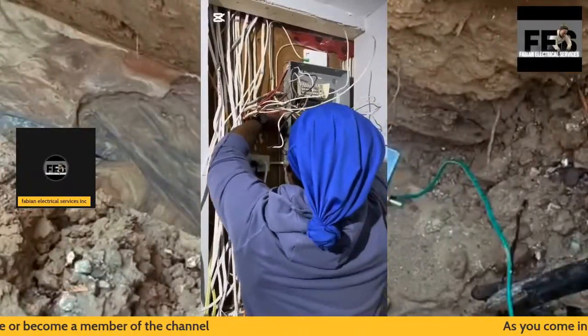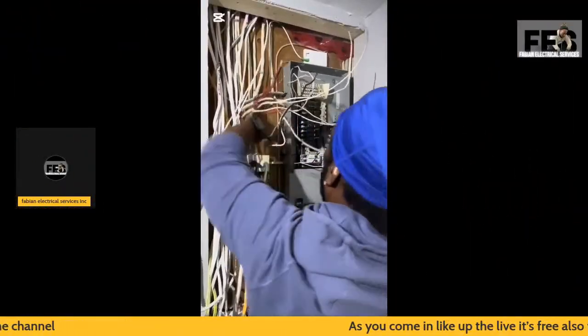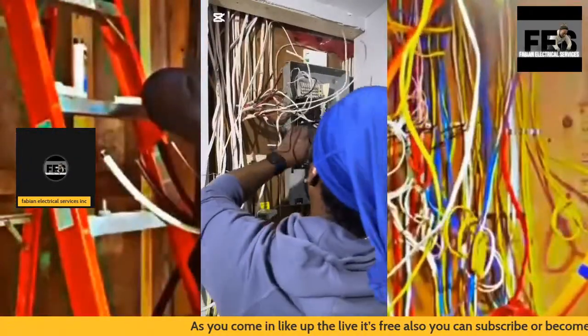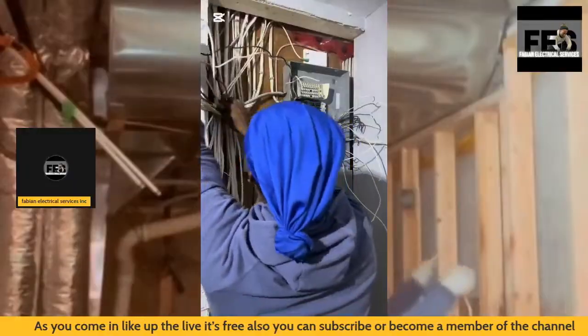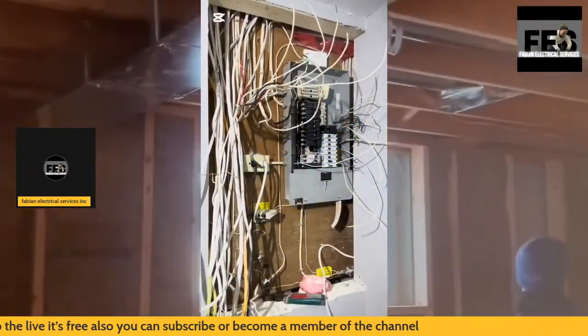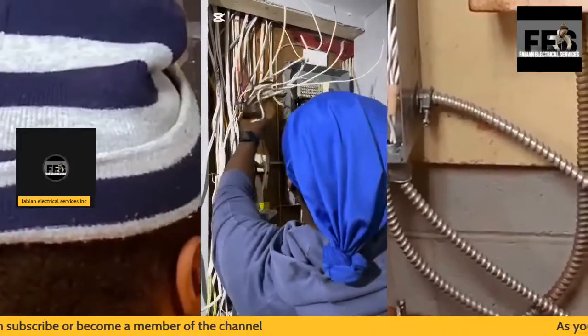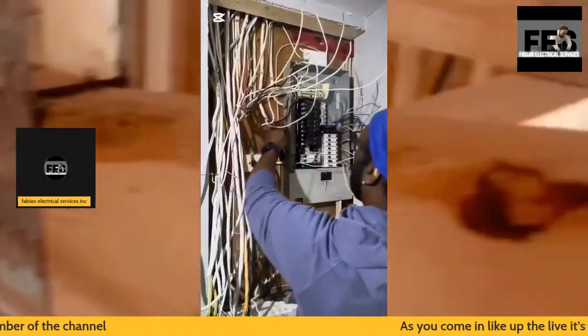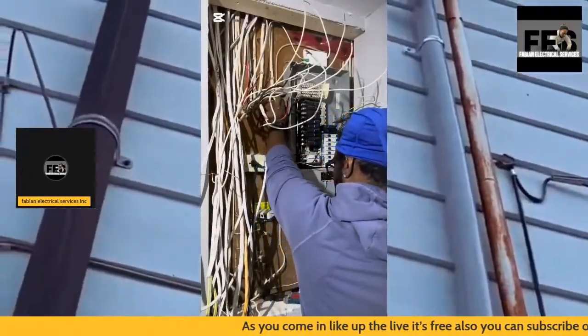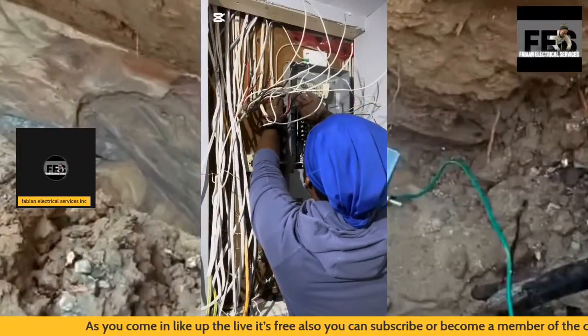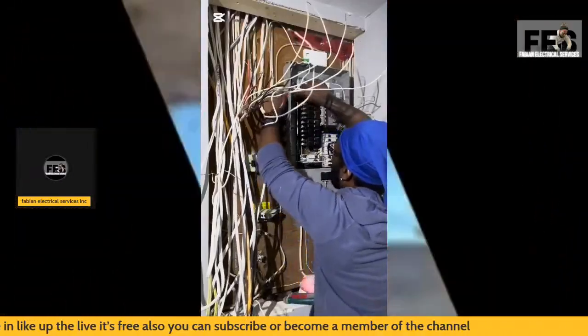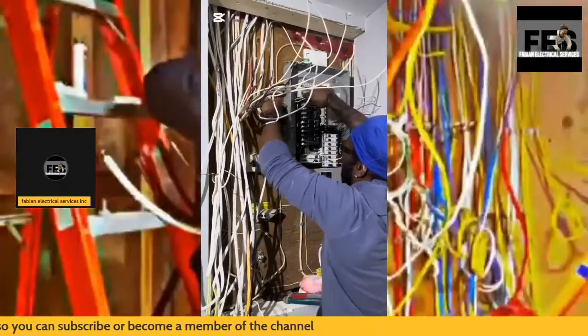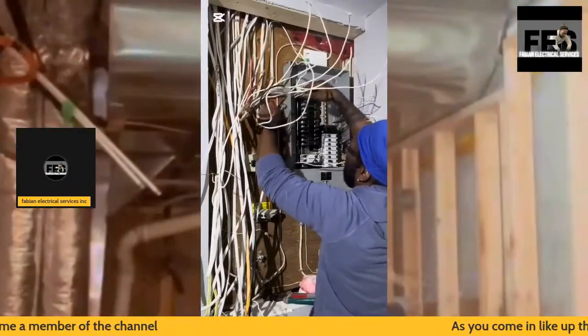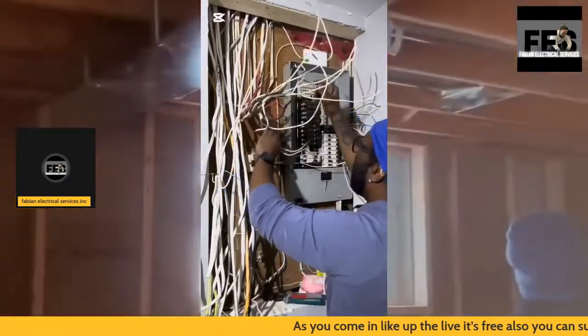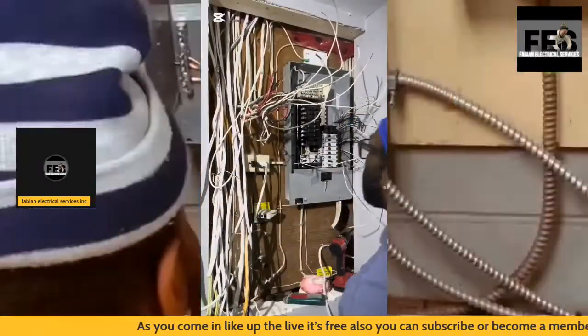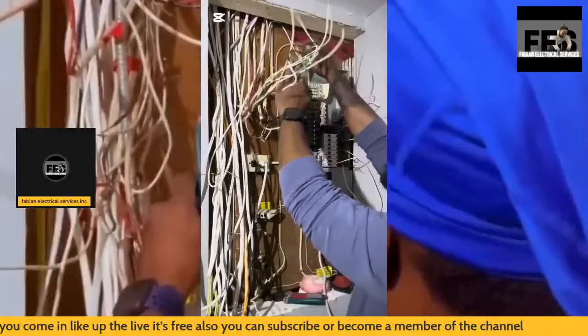A 100 amp Eaton panel is going to be installed in this location. My new panel is being flipped in the other direction because the main electrical wires coming in from the outdoor meter base come in on the bottom. In order to make my installation work, I have to turn the panel the other way, so the main breaker faces downward towards me instead of in the upward position.